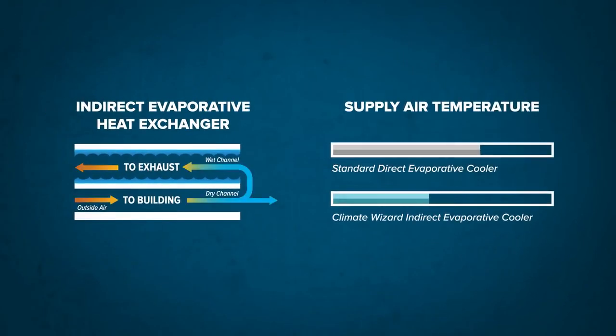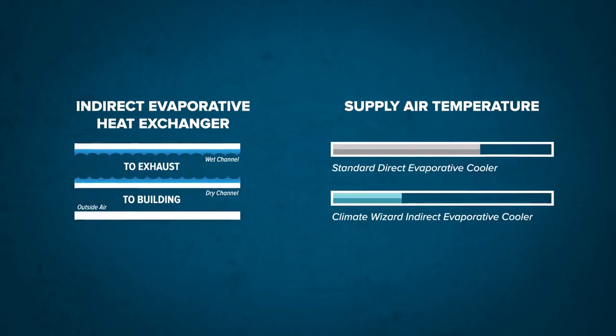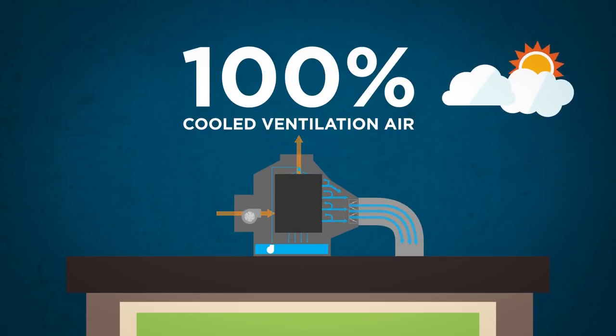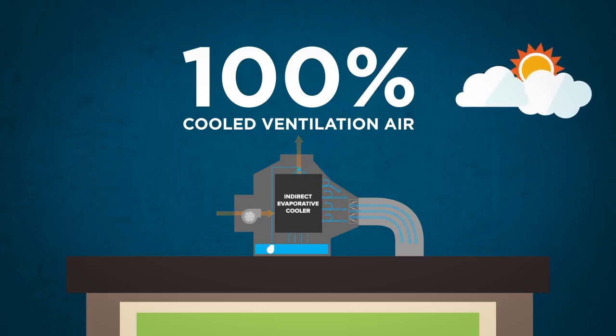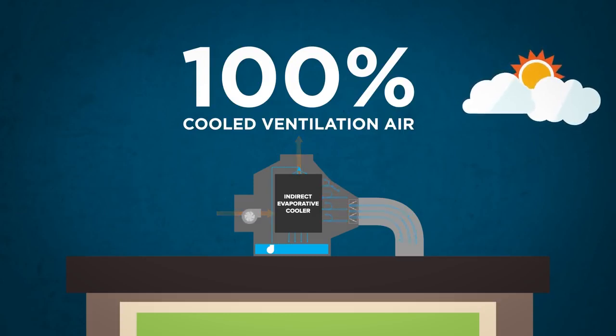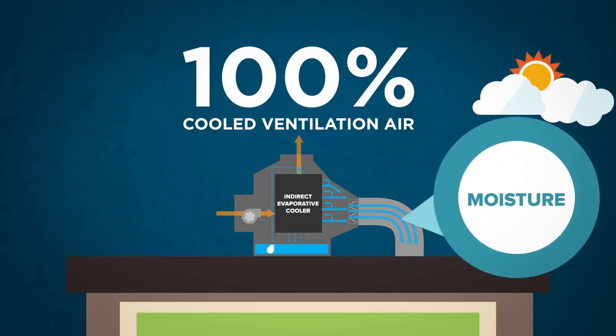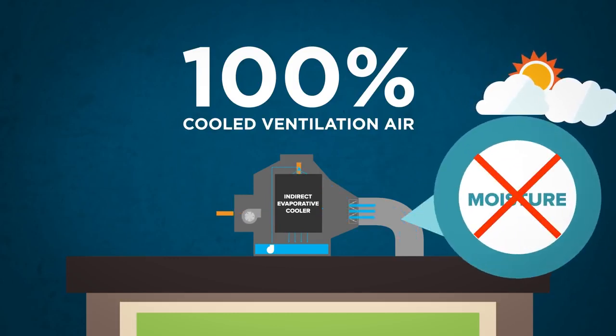This process allows the Climate Wizard to deliver air to the building at a much lower temperature than traditional evaporative systems. This has benefits for both energy consumption and occupant comfort. Delivering 100% outdoor air, the Climate Wizard can improve indoor air quality by increasing ventilation rates to a building. Because it uses indirect evaporative cooling, where the wet channel air cools the dry channel air without any direct contact between the two, Climate Wizard does not add humidity to the building. So, although the system uses water to achieve evaporative cooling, only heat is exchanged and no moisture is added to the building.